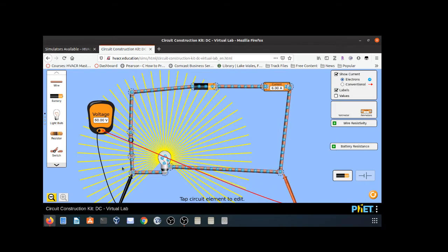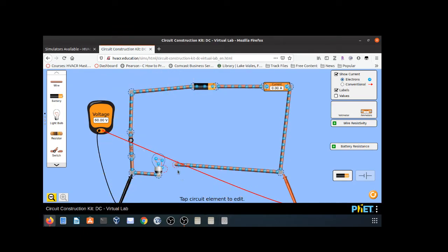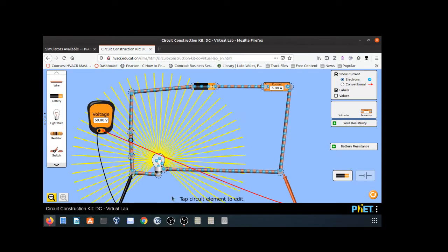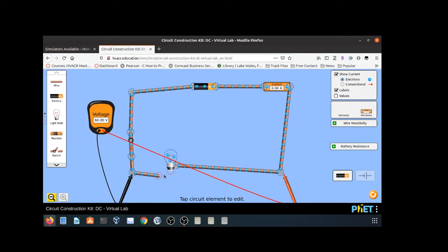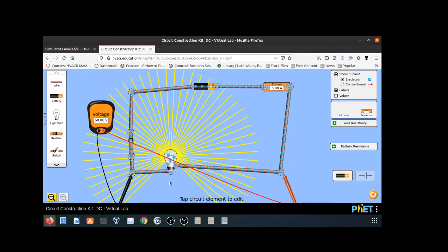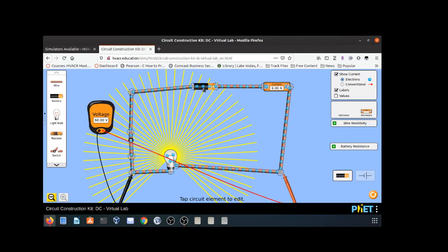What about measuring voltage across a load? If I break the wire connection, I have 60 volts — and with the circuit complete, I also have 60 volts. Voltage across a non-working load is source; voltage across a working load is also source. How do you tell the difference? Your meter tells you if voltage is present, but your eyes tell you if it's working or not. This is what comes into troubleshooting.